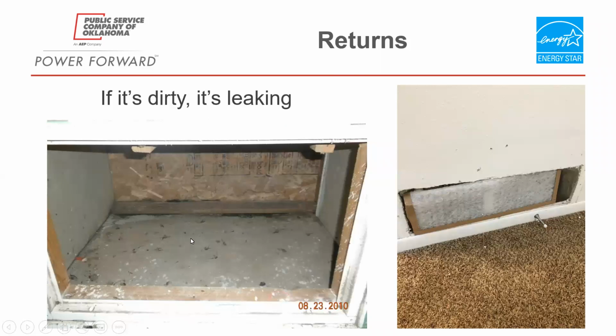This is a return right here. One thing I tell everybody is that if you see a return like this with dead cockroaches or dead bugs, or debris, dirt, sand, all kinds of stuff down here, not only do we need to clean that out, but it also tells me that return is pulling air from places it shouldn't be. All of these connected pieces should have mastic on them, because that air is being pulled from attic spaces, crawl spaces, and interstitial walls — places we really don't want to be breathing air from.